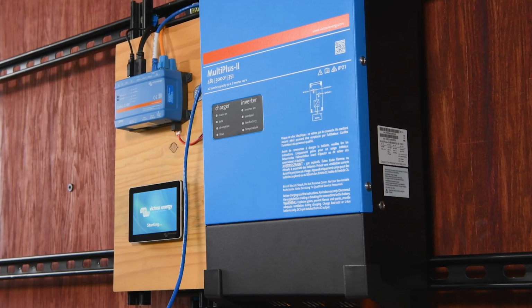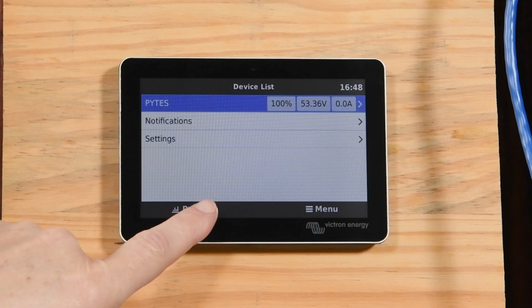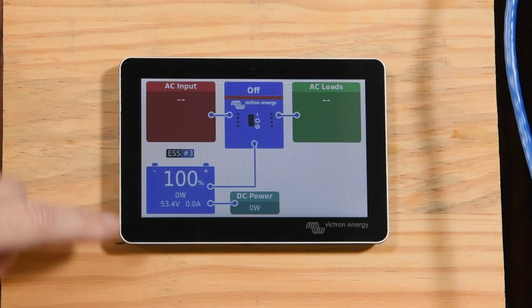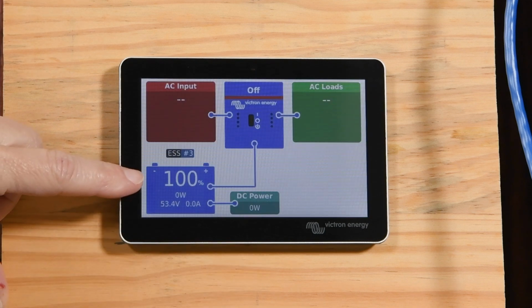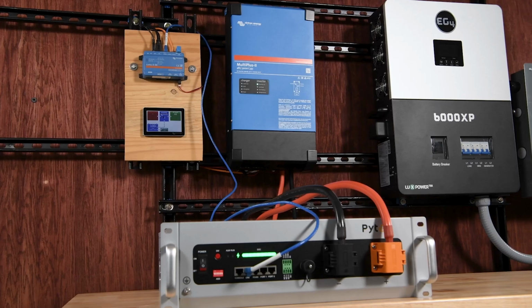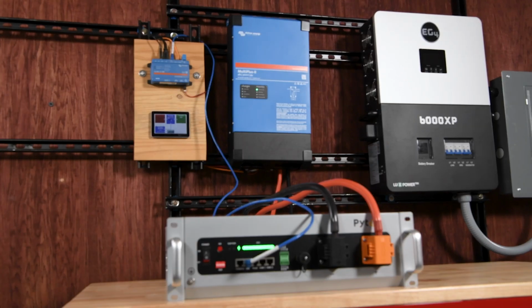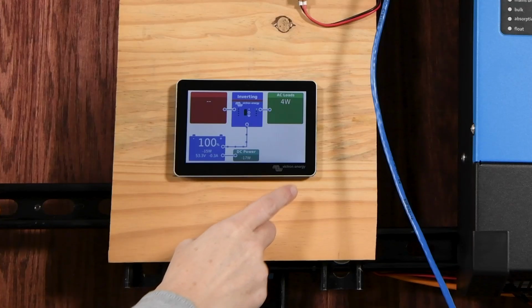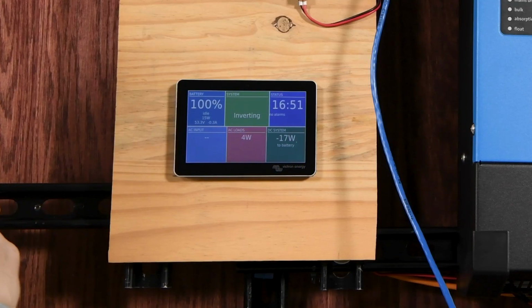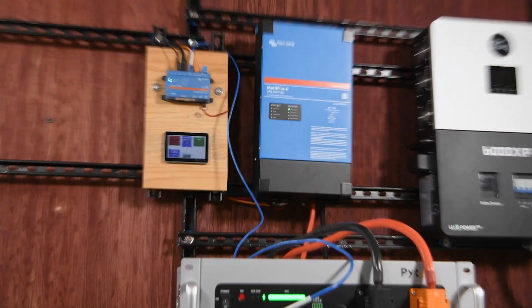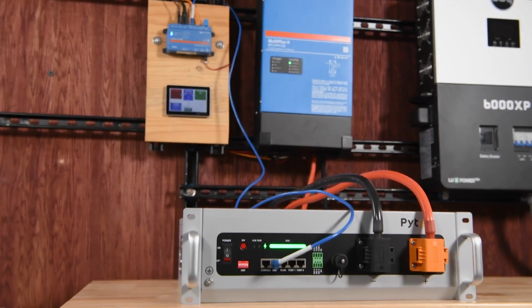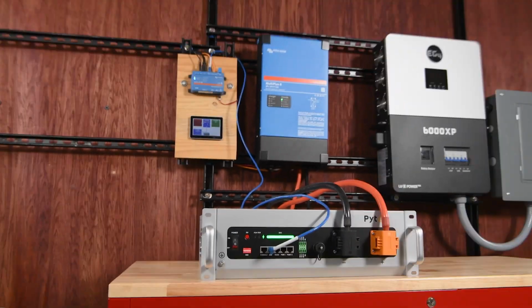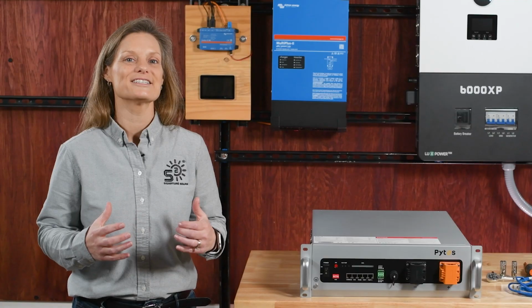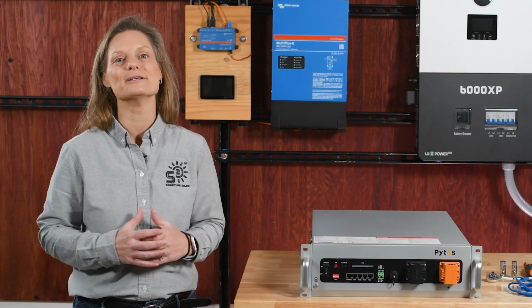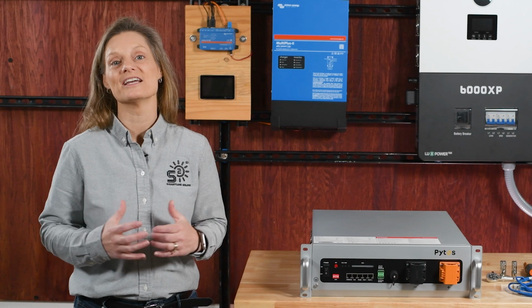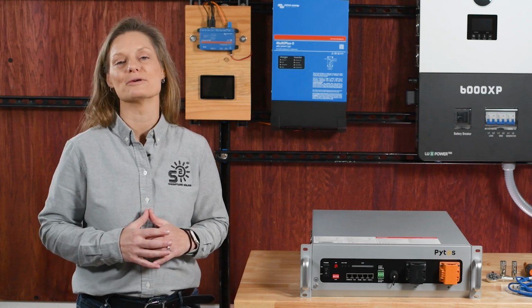Once the Victron system is up and running, we may need to adjust some settings on the GX touchscreen to confirm the system is communicating properly. If everything's connected correctly, we should see the state of charge percent displayed on the screen. The SOC percentage is showing as expected, indicating a successful connection with the Victron setup. This compatibility highlights the flexibility of the V5, which can connect seamlessly with many inverter brands.